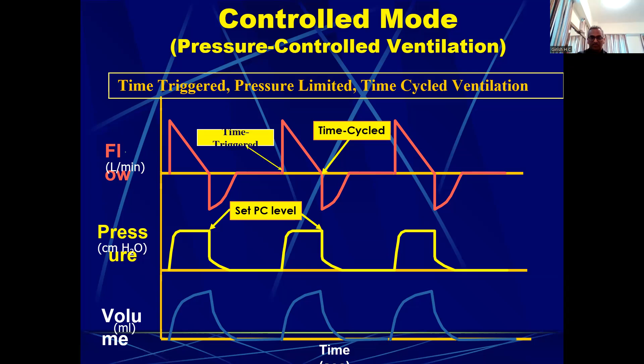So this is time cycled, time triggered, and pressure controlled. So this also can be volume controlled, right? Instead of setting the pressure, if I set the volume, then it becomes volume controlled ventilation. Okay.